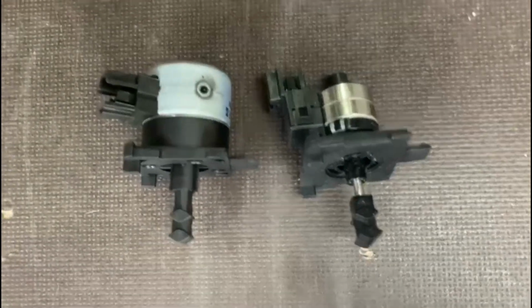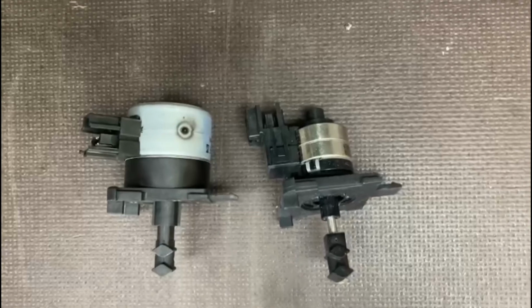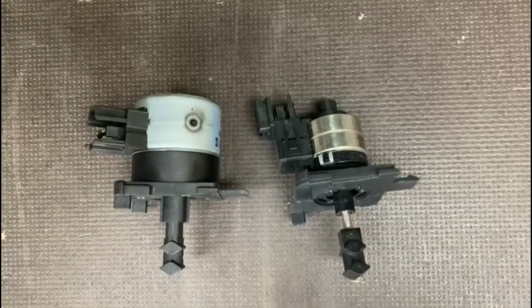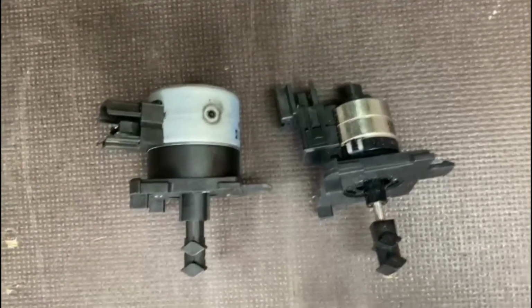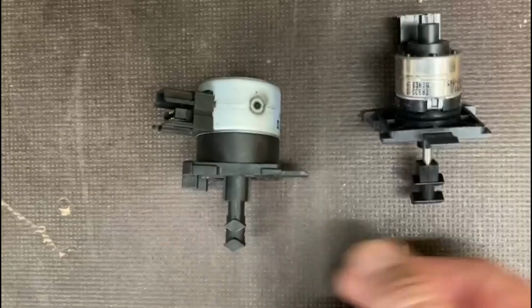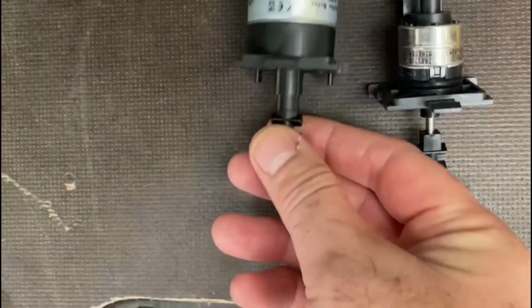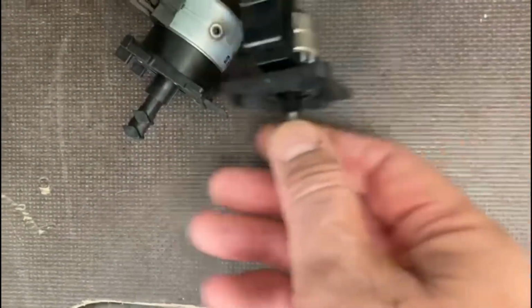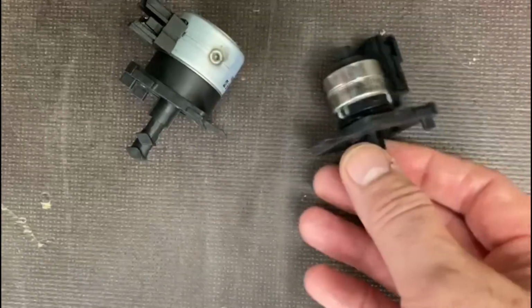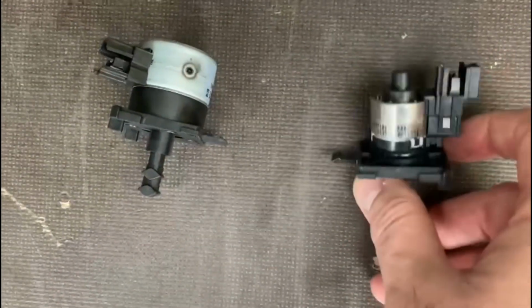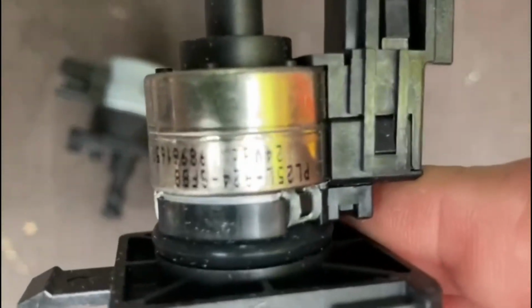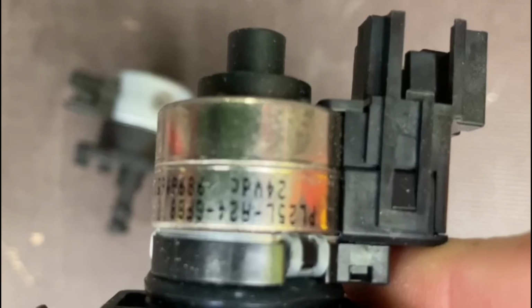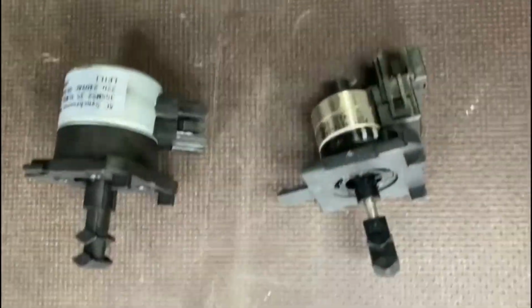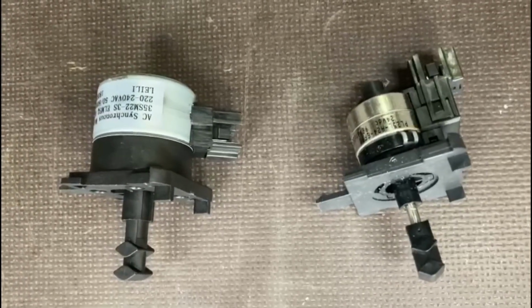I'm going to talk about how you test these, how they work, and what you can do to repair them if they get stuck. So they look very similar on the bottom half of the body. This section here is pretty much the same, and they fit into the same paddle, but the difference is the motor itself. This one's a 24 volt motor. I don't know if it says it on there. Yeah, it does. 24 volt DC. This is a 240 volt motor. Yeah, 240 volt motor.